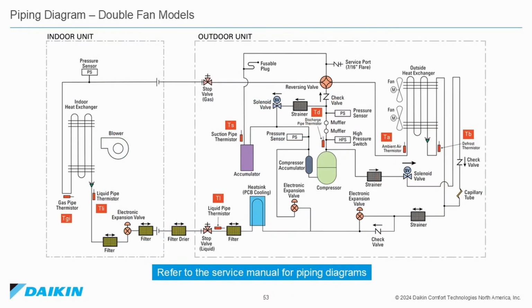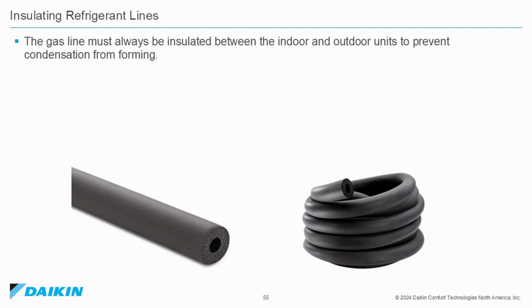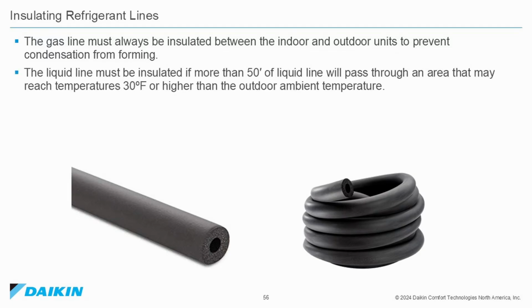Here is a piping diagram example for double fan models. Insulating refrigerant lines. The gas line must always be insulated between the indoor and outdoor units to prevent condensation from forming. The liquid line must be insulated if more than 50 feet of liquid line will pass through an area that may reach temperatures 30 degrees Fahrenheit or more above outdoor ambient temperature.